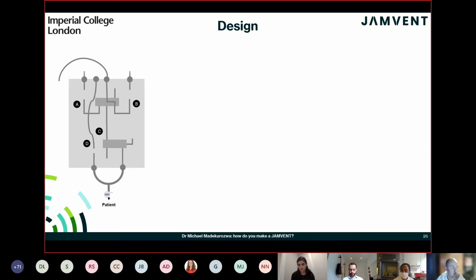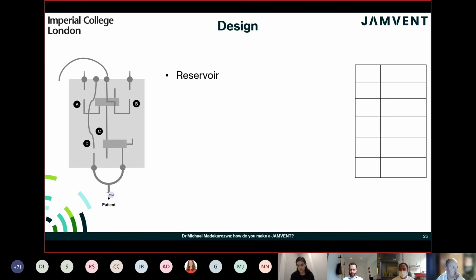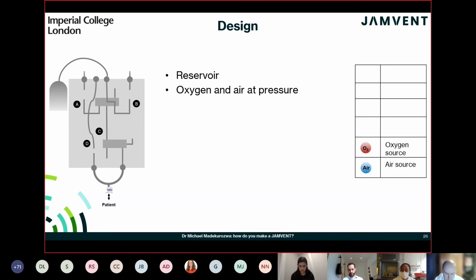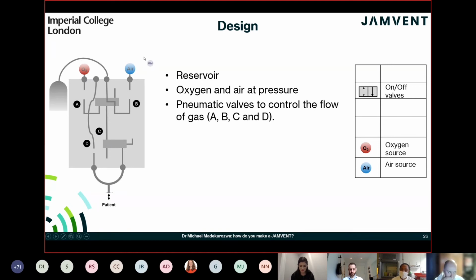So I'll go through a schematic of the system so that you can get a better appreciation of how it actually works. So first of all, we've got a reservoir. This is where the air to oxygen mixture is prepared and then at the correct tidal volume before being delivered to the patient. We need air and oxygen. So an air and oxygen supply are connected to the system as shown in the diagram over here and here. And then we've got pneumatic valves to help control the flow of gas. So here are the pneumatic valves, B, A, C, and D. So these are just on-off solenoids.